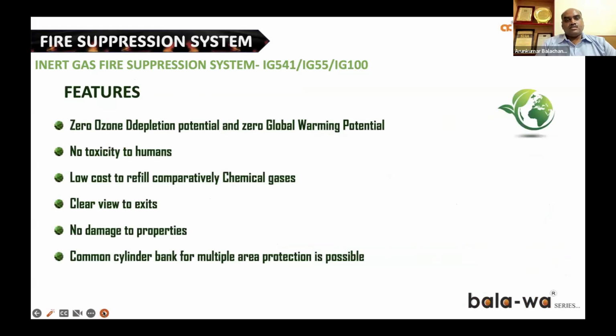Some of the features of the inert system are, as I said earlier, zero ozone depletion and zero global warming. It has no toxicity to humans when designed correctly within the NOEL and LOEL levels. The cost of refilling is very low compared to chemical gases. During discharge, the inert gas gives a clear view so that people inside can start to exit even when the discharge starts. There is no damage to property as inert gas does not react with materials. And the inert system can be designed with a common cylinder bank for multiple area protection.